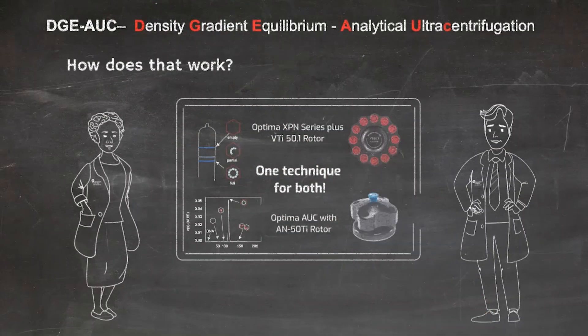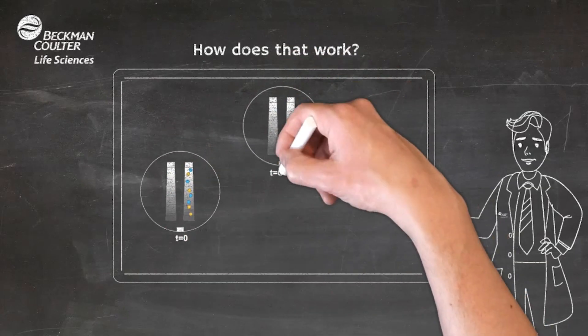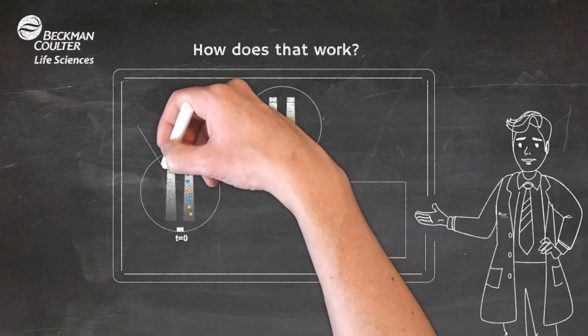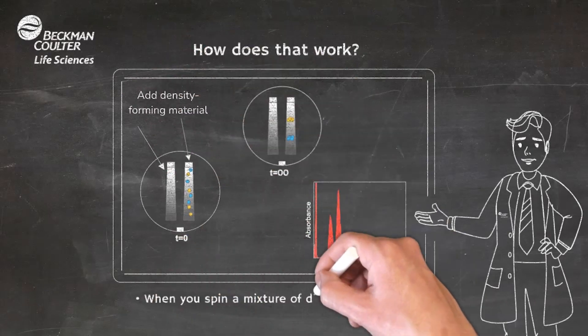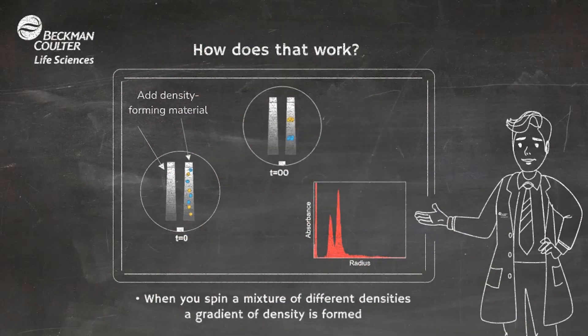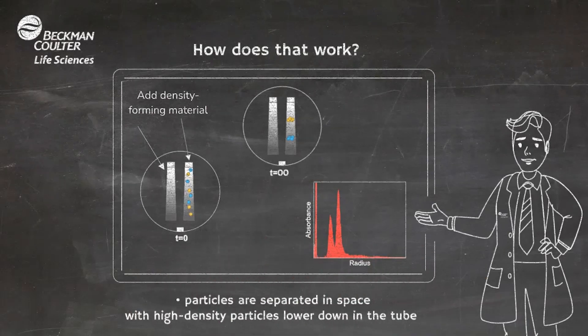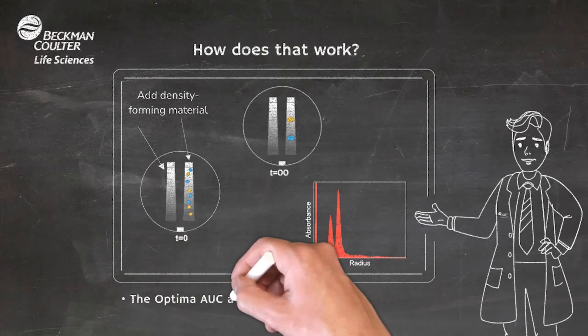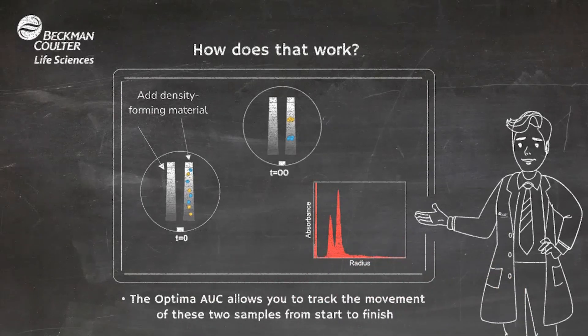How does that work? When you spin a mixture containing particles of different densities — such as empty and full capsids — in a solution containing a density gradient forming material like cesium chloride, a density gradient is formed. At the end of the experiment, the particles are separated in space, with the high density particles lower down in the tube than the low density particles. The Optima AUC allows you to track the movement of these two species from start to finish.